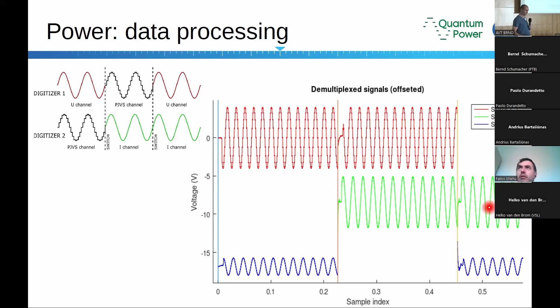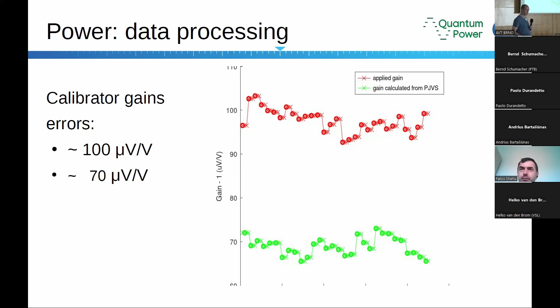Again, the sampling card had quite big errors. The first channel had about 100 microvolts per volt gain error. The second was 70 microvolts per volt error. So it's an error much bigger than our final errors. So we know the system works. And these are the results.